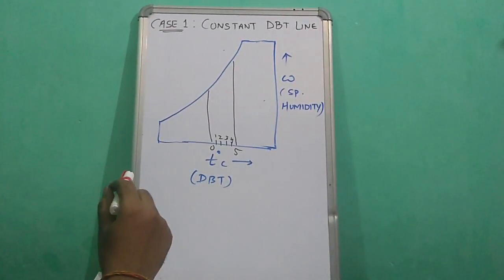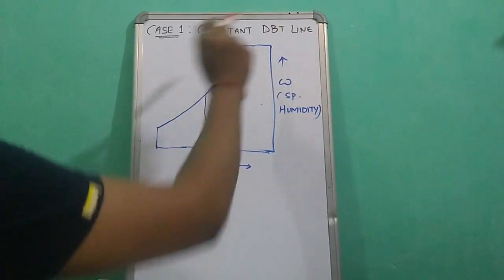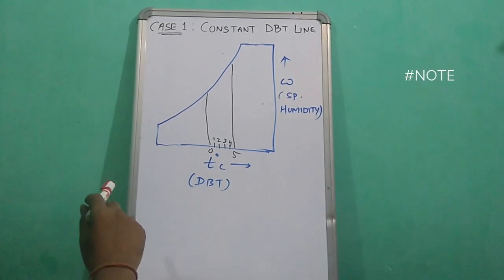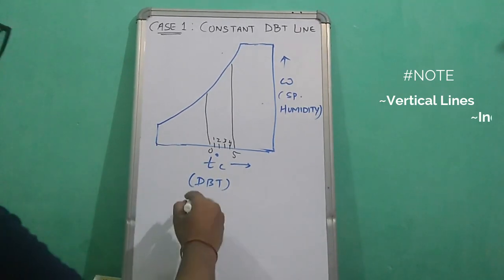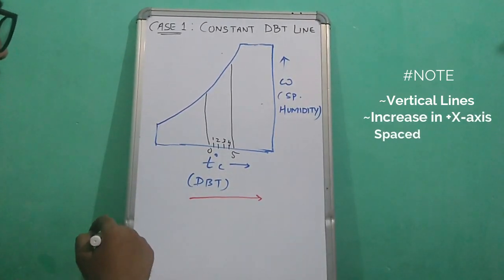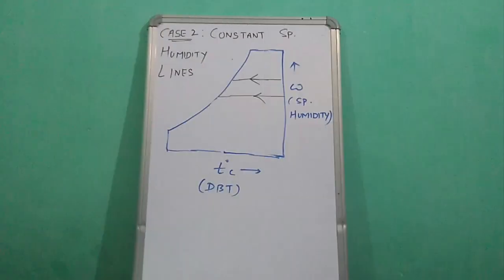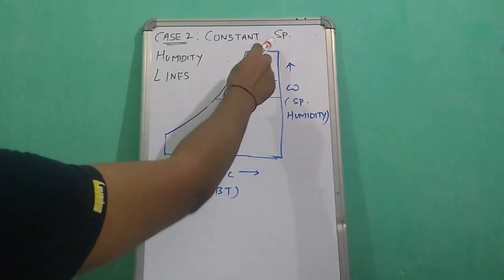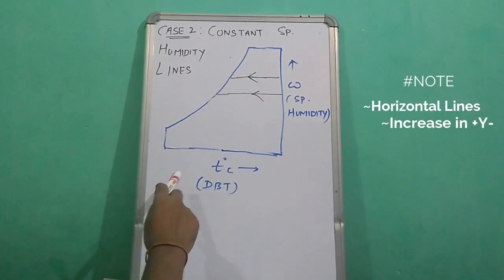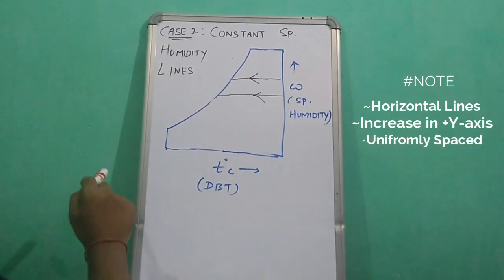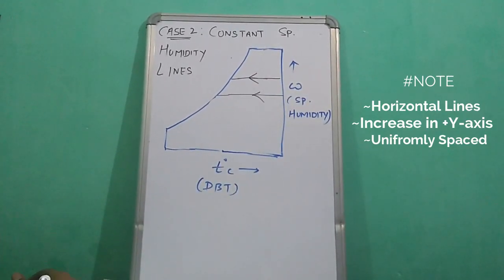Let's represent the different constant parameters on the psychrometric chart. Case 1: constant dry bulb temperature lines are vertical lines on the psychrometric chart, increasing in the positive x-direction. Case 2: constant specific humidity lines are horizontal lines moving towards the saturation curve, increasing in the positive y-direction, and are uniformly spaced.